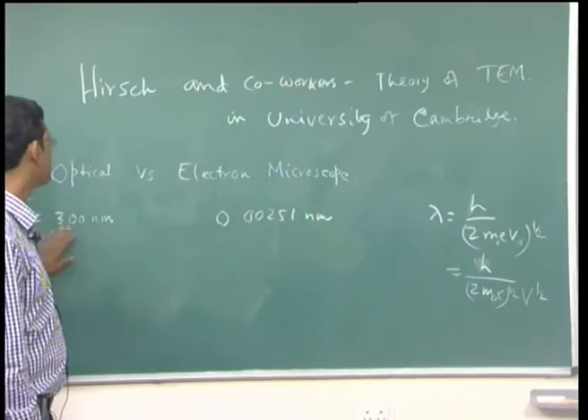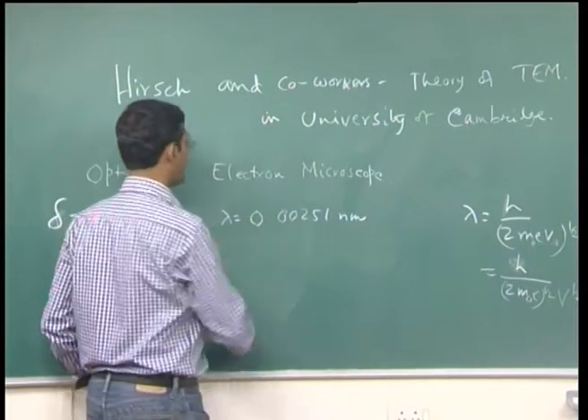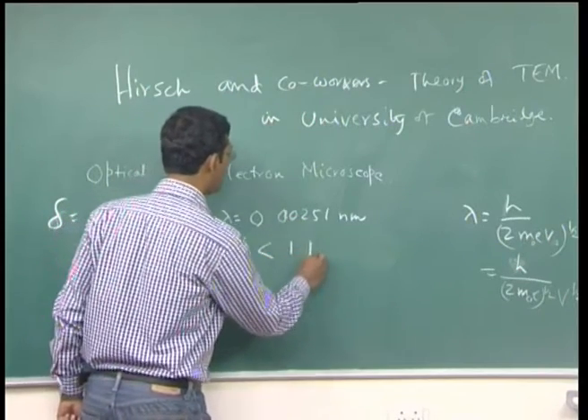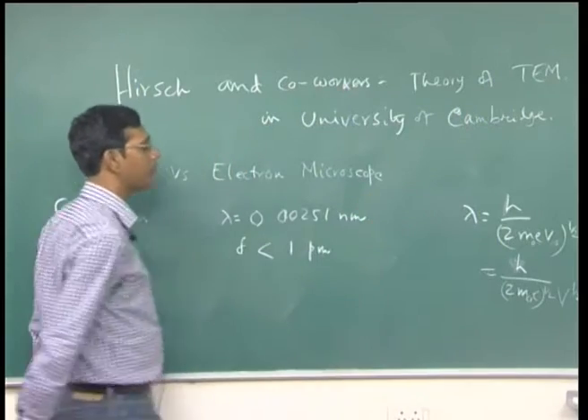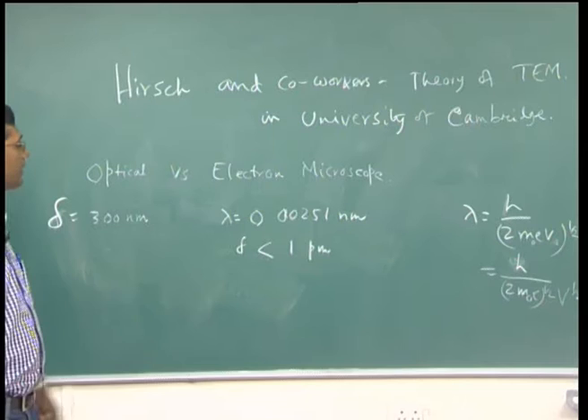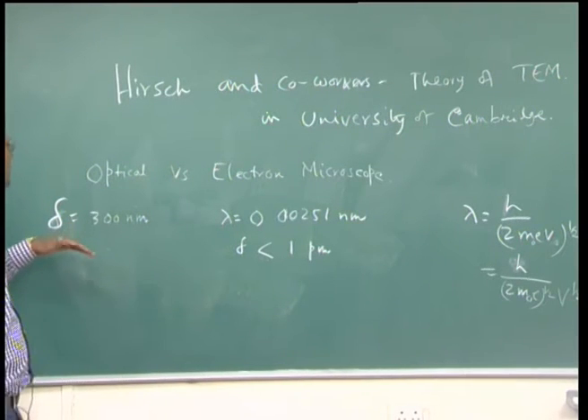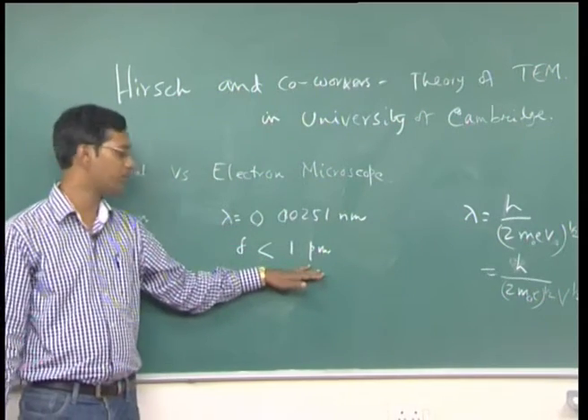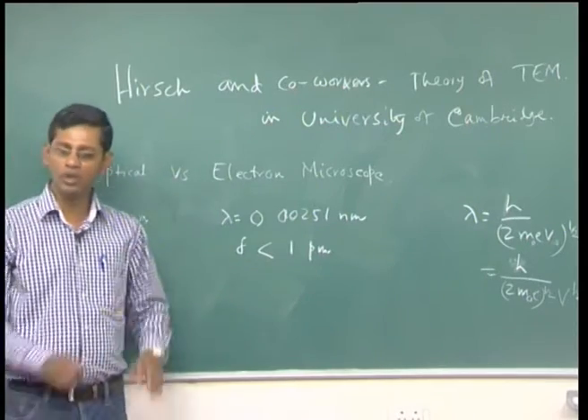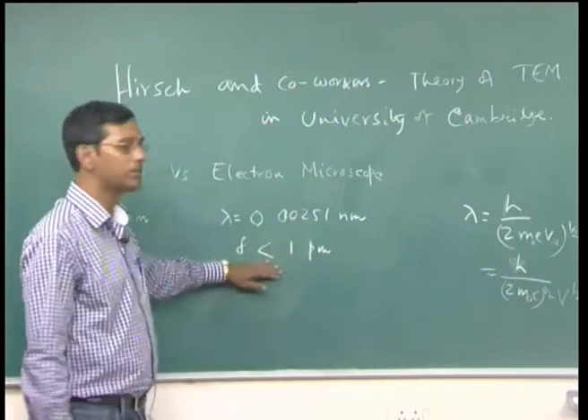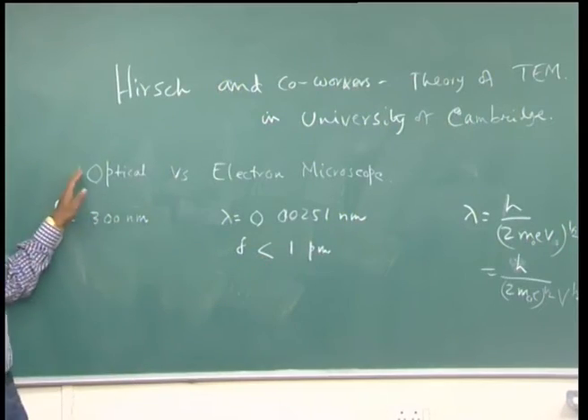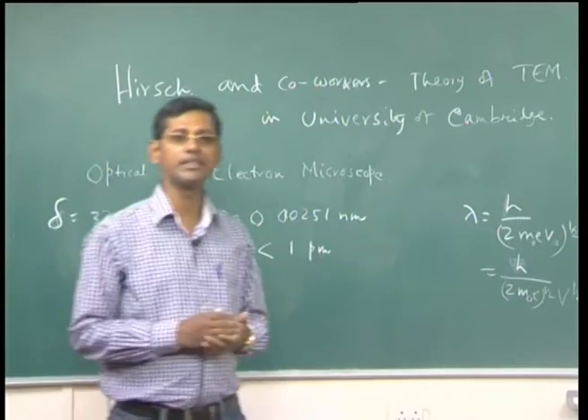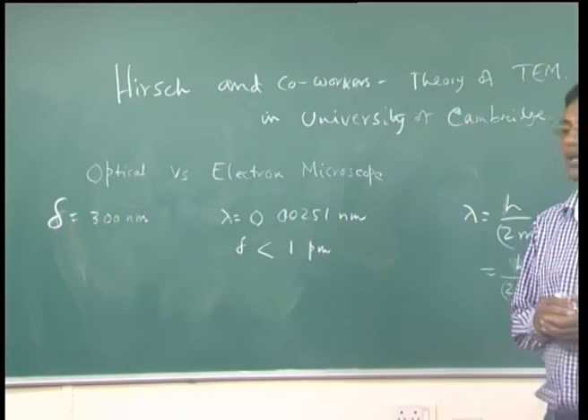So immediately you can see that if lambda in the electron microscope is that small, then the resolution δ will be less than 1 picometer according to the Rayleigh formula. One can clearly see that it is possible to reach resolution theoretically from 300 nanometers in an optical microscope to less than a picometer in an electron microscope. However, we do not normally achieve this resolution because of problems with the lenses.